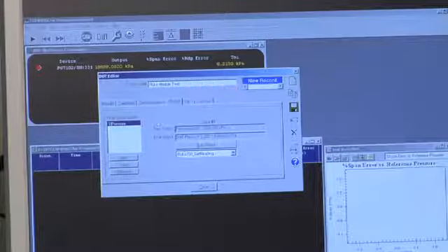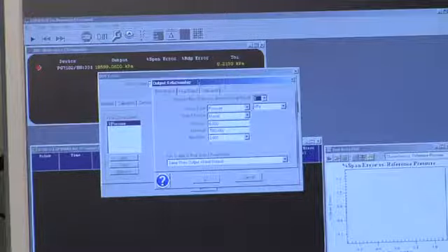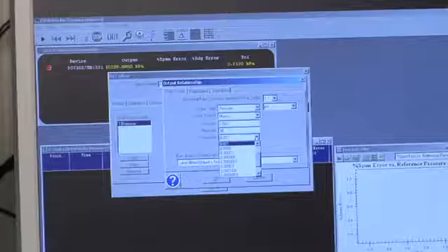So if I go to the output tab, I see now there's a pressure range and a selection of a macro that's going to be used to interact with this device. So this range, of course, the software doesn't know the range because I just chose an example. If I double click this field, I can define the actual range of the instrument. I can define the resolution associated with the device. This is very important because if you have the wrong resolution, your data is not going to come out the way you expect it to.